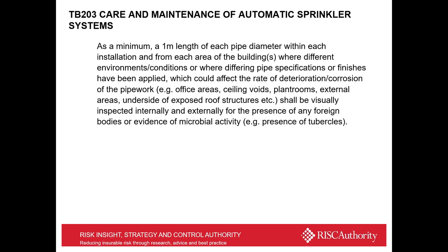So if you have five installations, you will need to inspect five installations and from each area of the building. This is because there are different environments and conditions where pipes are installed within a building. These could affect the rate of corrosion and deterioration of the pipework.